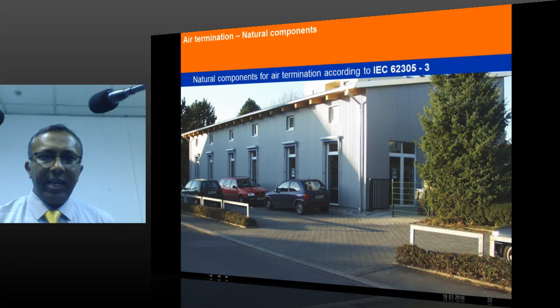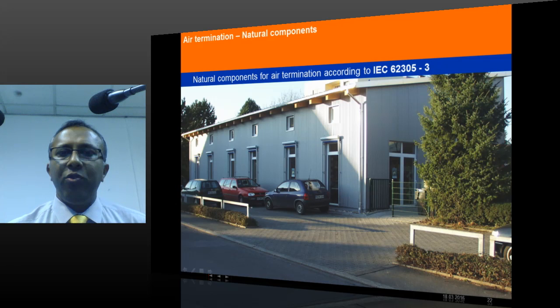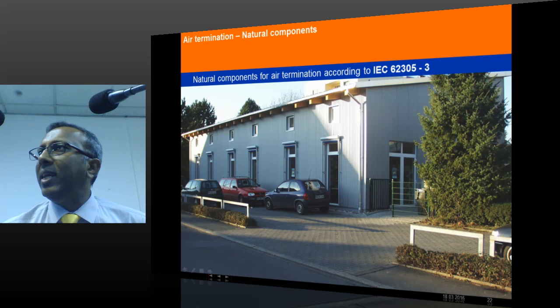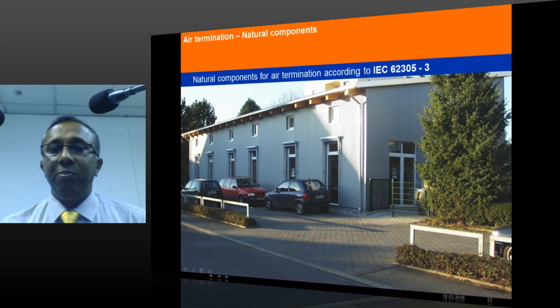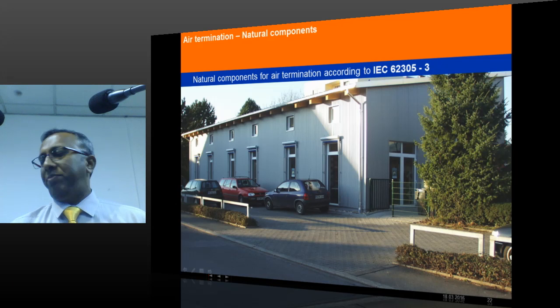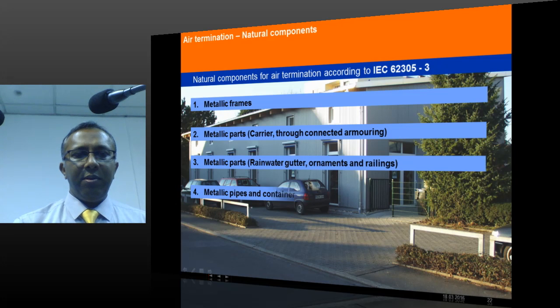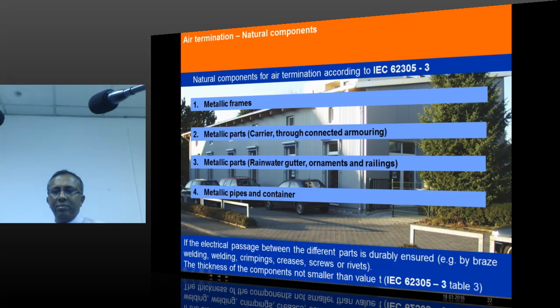You can see in this particular case a building with a steel roof, and this steel sheet at the roof may be enough, provided it is connected to ground through steel columns, metallic frames. So what the standard basically says is, in case of this kind of building, under certain conditions, you don't need an external protection system. Under certain conditions, it is underlined. What can happen is, in case of a lightning strike, your electrical apparatus will be in trouble. That needs internal protection. It is not connected to the external system.